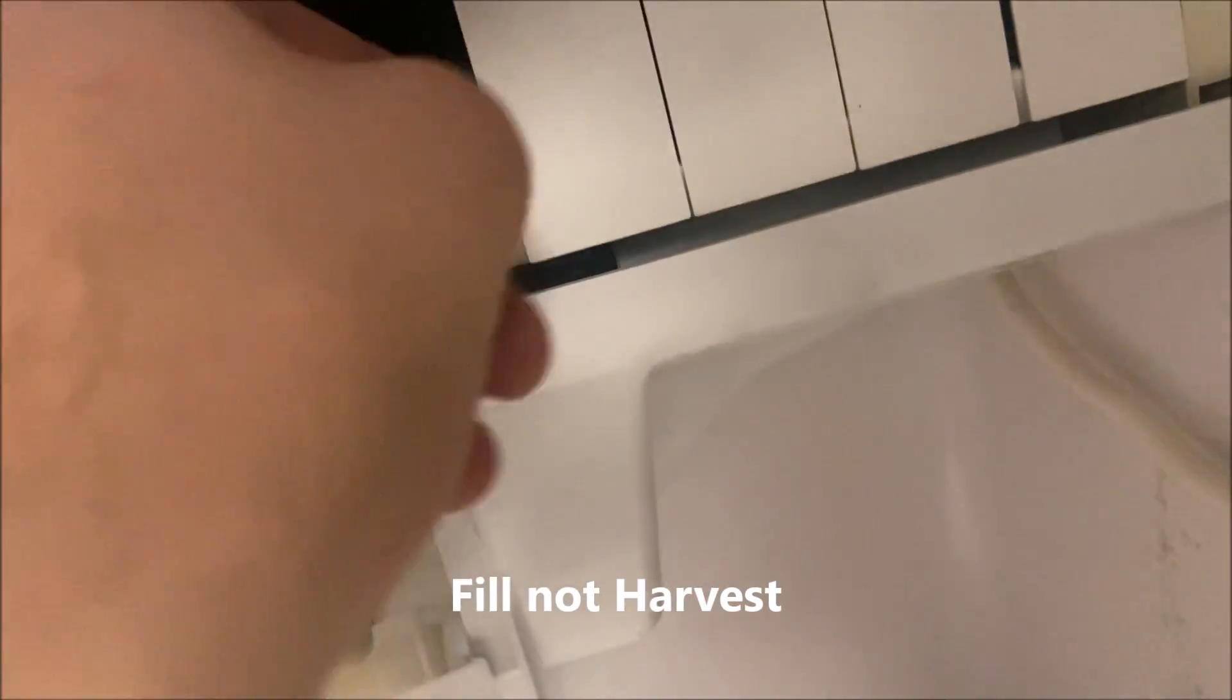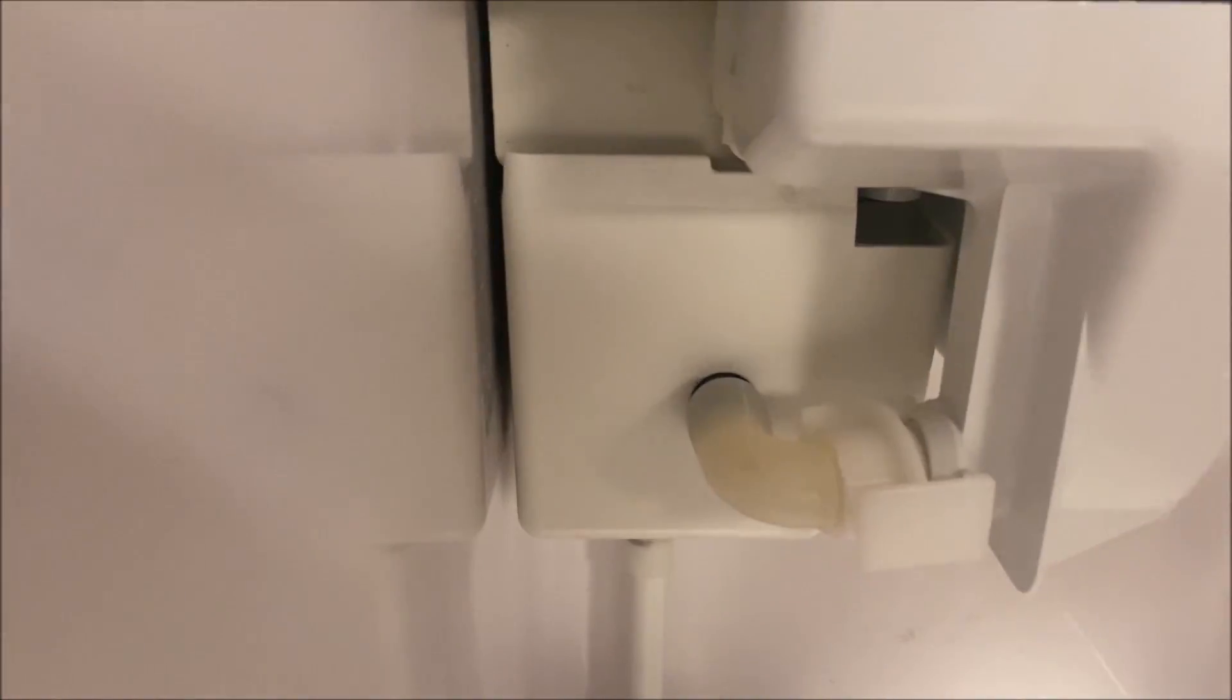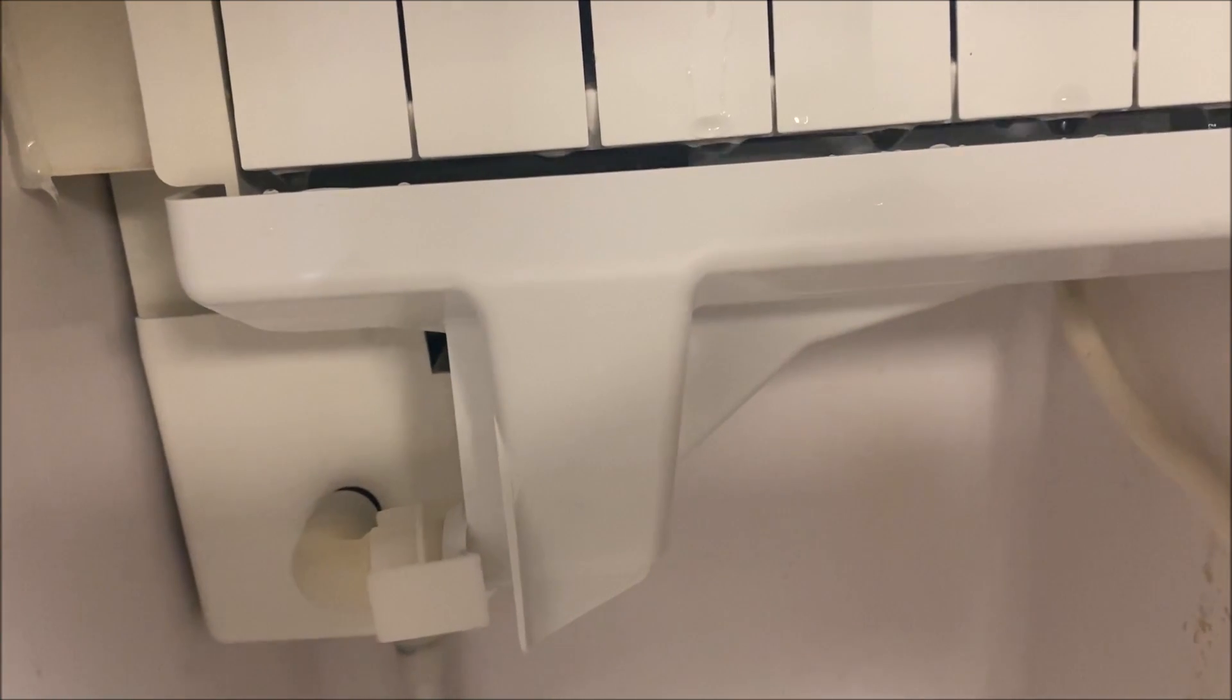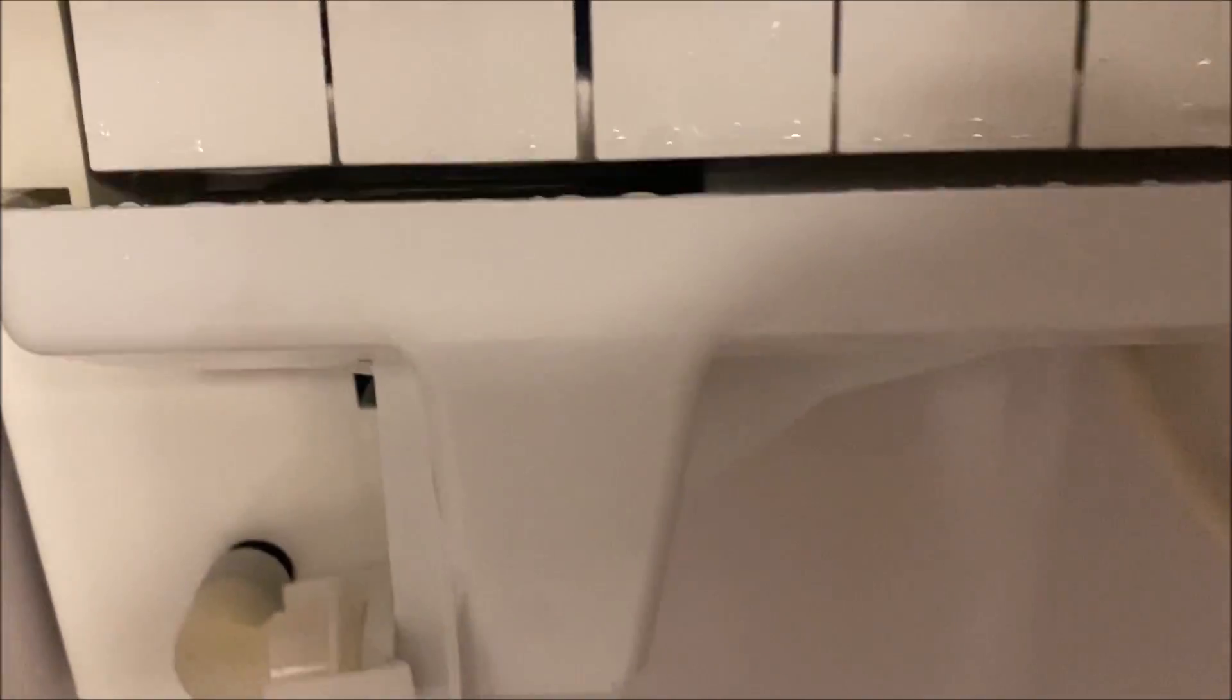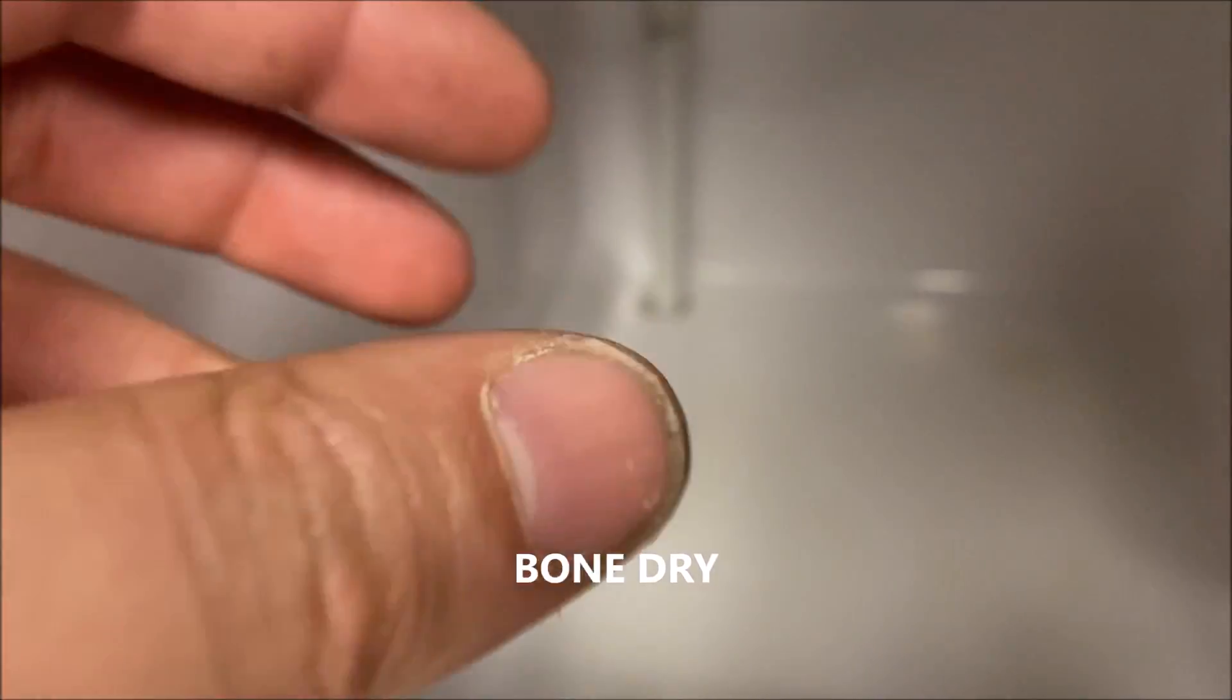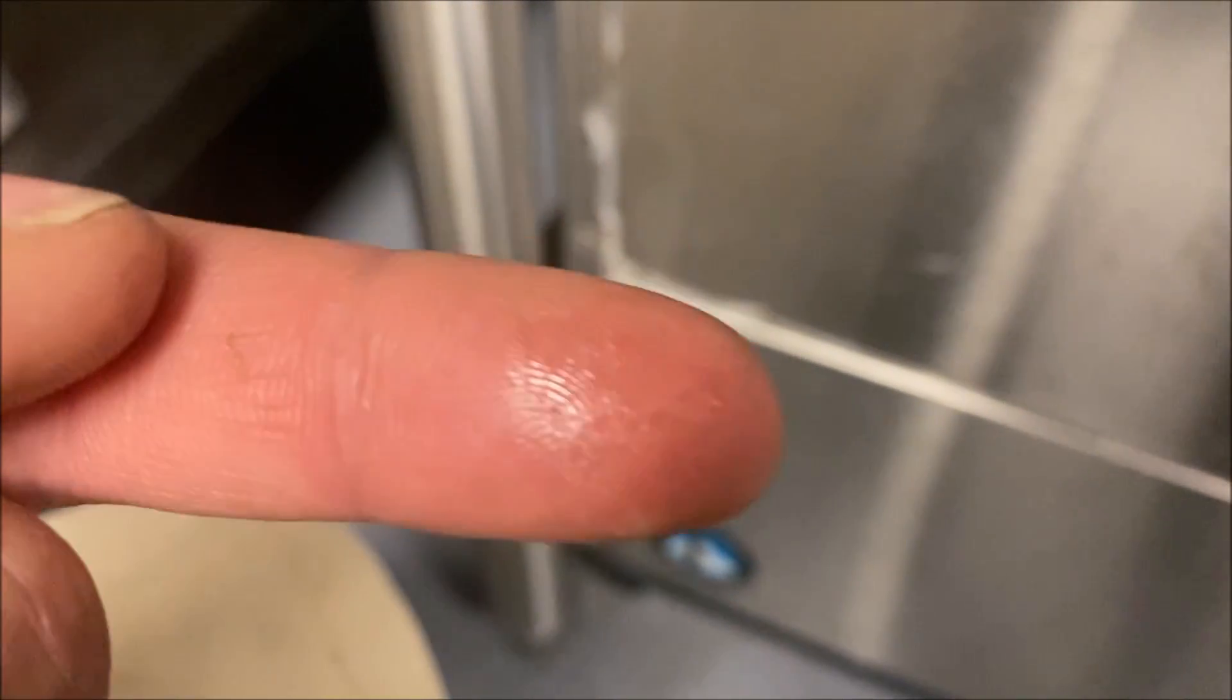And we are into harvest now. We're filling the trough again with our solenoid. You can see our pumps running. And look at that. She's dry. No water. It looks like this trough will resolve the issue. But obviously let's drop a batch of ice. Let's see what's going on. And still dry. There's nothing in this bin whatsoever. Look at that. So our water level in the trough is maintaining. It's transferring the water from the trough onto the coil. We have a little bit of a drip on the edge here but it's so minimal. It's not even getting down to the ice bin.